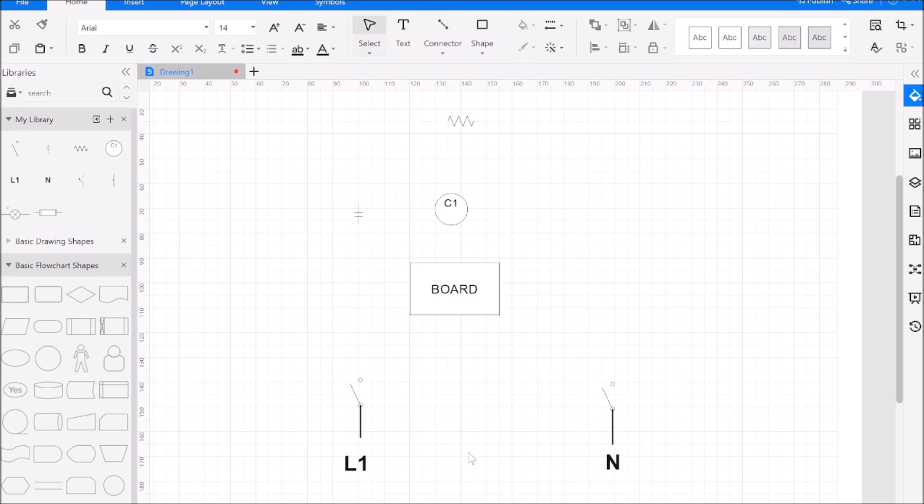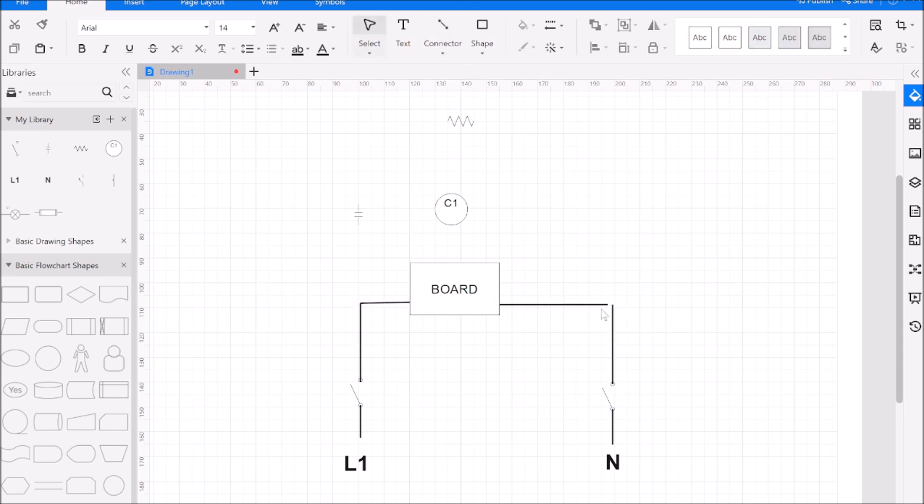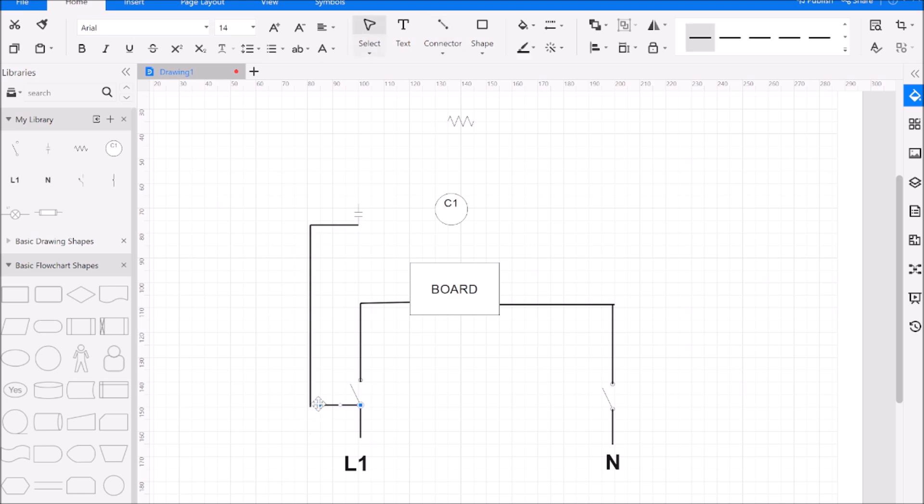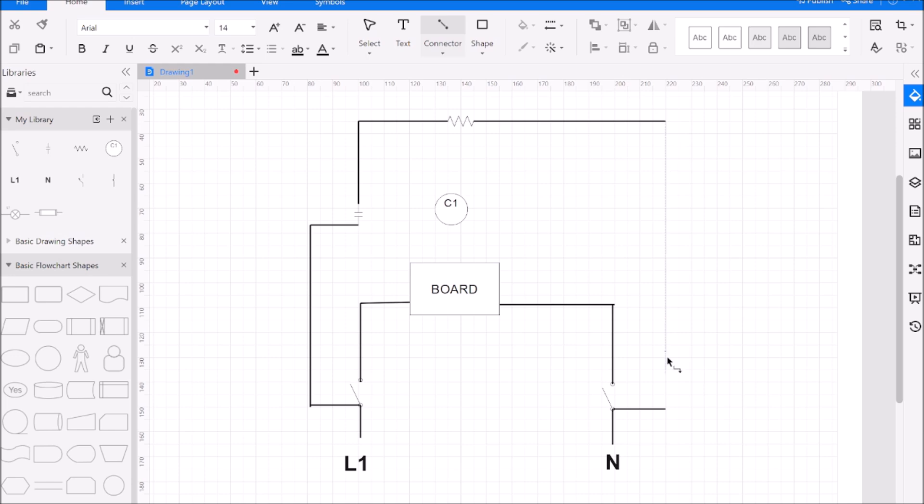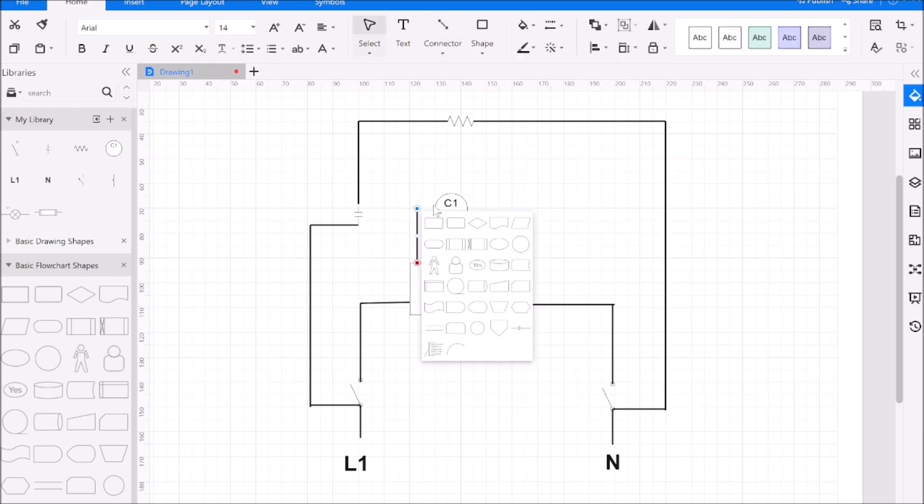So L1 and neutral straight shot to the power switch. On the outlet of the power switch we're feeding the board. And then next we're going to bring in power to our relay contact, so that's coming directly off the switch. Our contact feeds that element, and then our neutral side on the incoming side of the switch is a straight shot to our element.